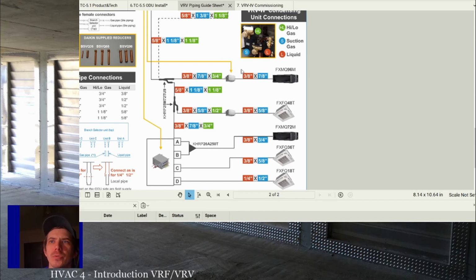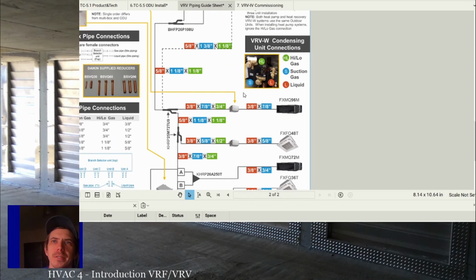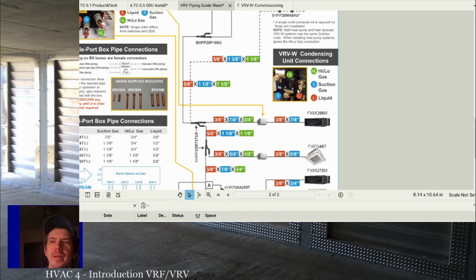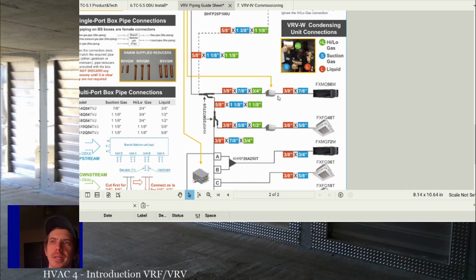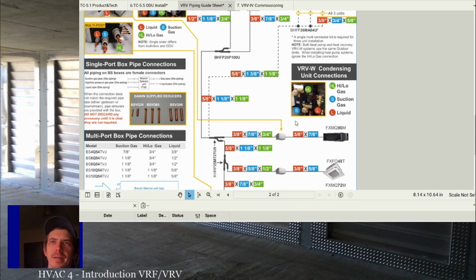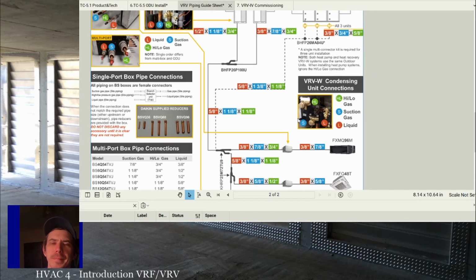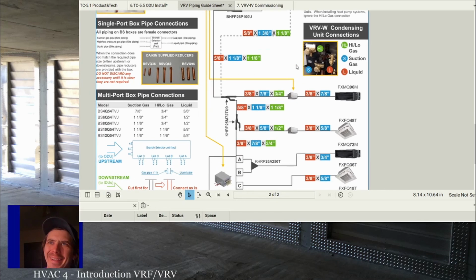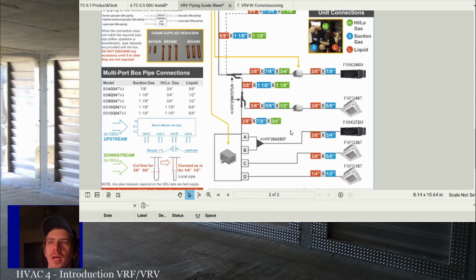Now, there can be situations where the thermostat goes to the branch selector. I could be misremembering that. It's going to daisy chain to the branch selector, and then the branch selector can go to the thermostat, or the indoor unit can go to the thermostat. I may be misremembering that. Maybe I'll try and pull up a wiring schematic. But the point is that all the branch selectors daisy chain, and then all the indoor units are connected to that branch selector daisy chain, and then either the branch selector or the indoor unit is going to go to the thermostat, and it just makes one long line.